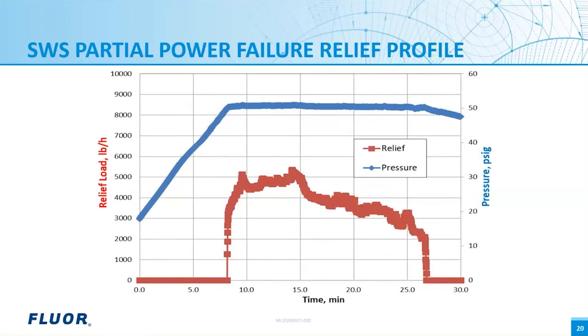This is the relief profile for the partial power failure case. In this case, the feed stops and the overhead cooling is lost as the pump-around pump stops, but the bottom product pump is working. This prevents the sump pan and reboiler return line from being flooded. As a result, the reboiler keeps working and inputs heat to the column for a relatively long period of time. A long relief profile — longer than 15 minutes — is identified by the dynamic model. This reflects the fact that the bottom product pump running during partial power failure allows reboiler circulation to be maintained until the column runs dry.